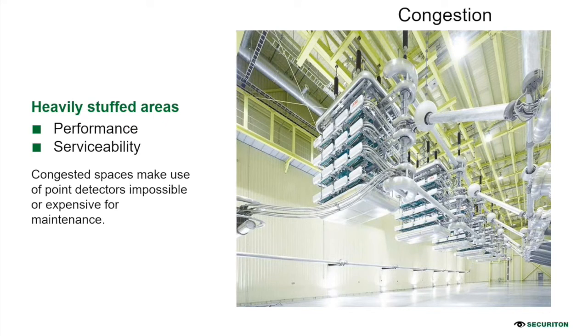Also, the congested spaces don't allow installation of point detectors. In the area you want to protect, you want detection, but it is almost impossible to install point detectors. There are congested areas, and machinery is arranged in a random manner. So even if you would like to have a point detector, it is not possible. If you go and see a real scenario of an HVDC valve hall installation, it is almost impossible.